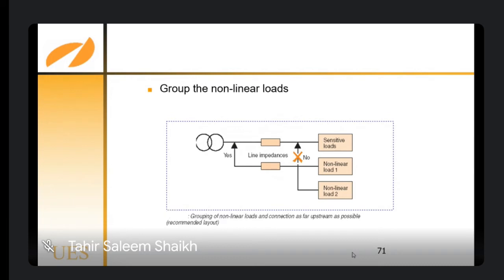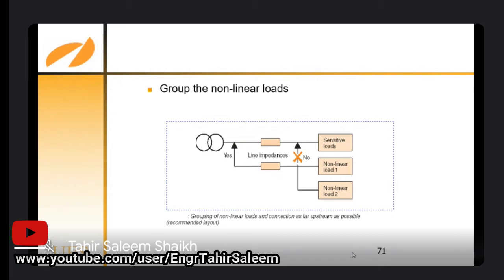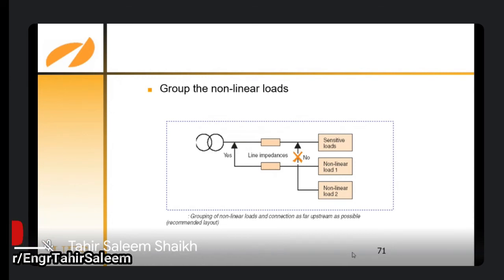And I have an example of this, where the nonlinear loads have a separate power input. There is a foundry here in Karachi, and the consultant designed the whole load as a single load. The load was about 1500 kVA, but that foundry also has induction furnaces.